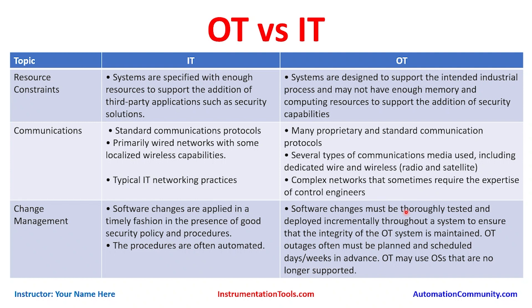In OT, software changes must be thoroughly tested prior to implementation and deployed incrementally to ensure the integrity of the OT system is maintained. You cannot simply receive a patch for a vulnerability and implement it immediately — it must be tested in a lab and released by the OEM before the asset owner can implement it. OT outages must be planned and scheduled; any shutdown or maintenance activity must be executed within the planned duration.